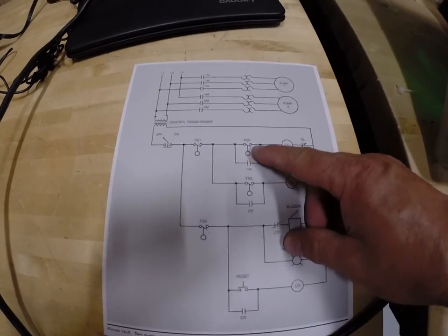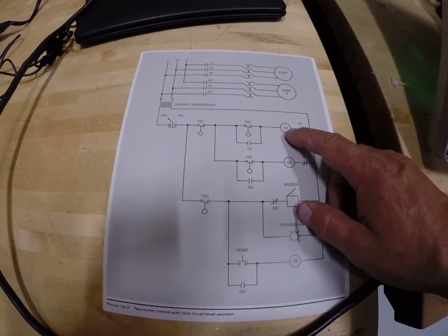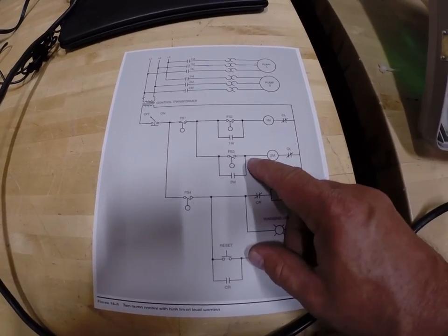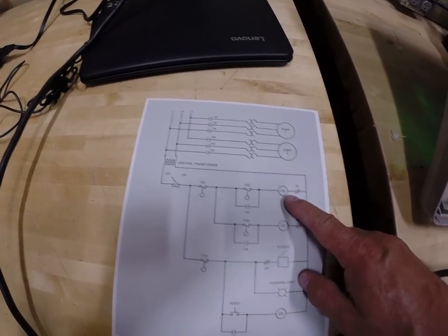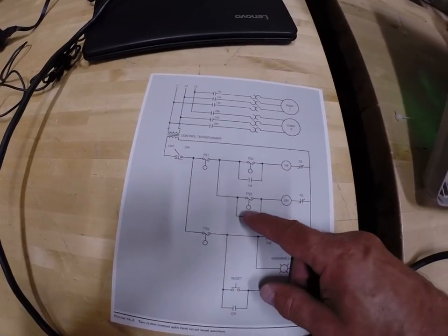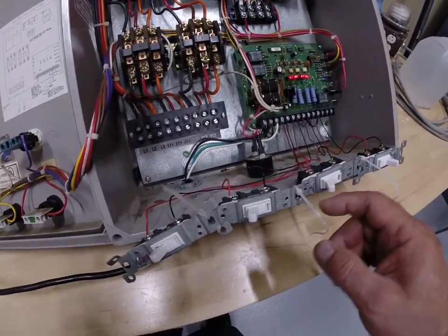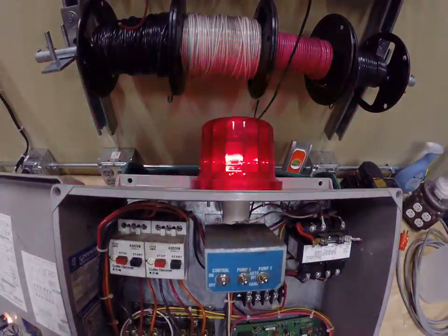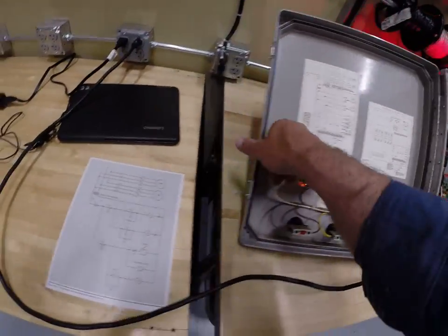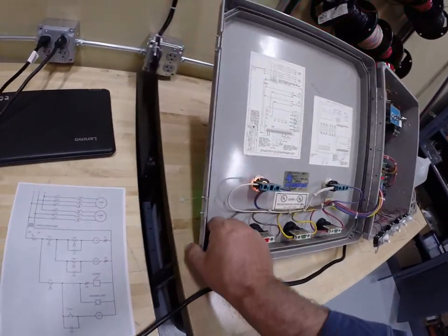I'm also going to hit, right at this stage of the game, pretend I have too much water. So right now 1M is running, we know because that contactor is pulled in. If I hit float switch number three, it's basically saying this pump ain't keeping up with the water flow. It's working, but we've got too much water coming in. That's why this float is activated, and it's telling another pump to run. So I'm going to hit that one. And right now the other contactor pulled in. The indicator light is on saying we've got a warning. I'm going to silence the horn right now so we don't have to hear that.